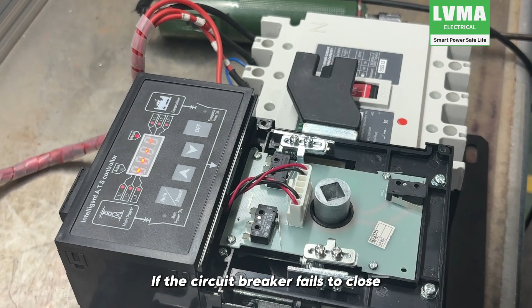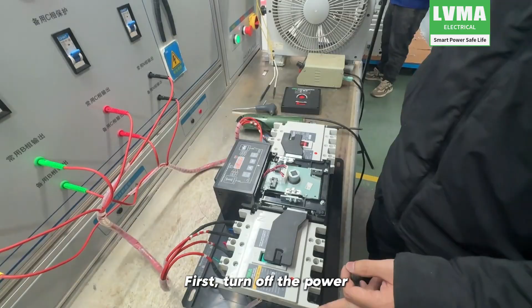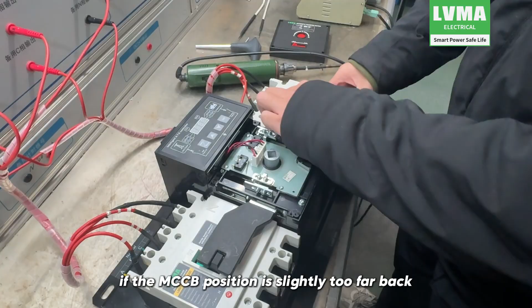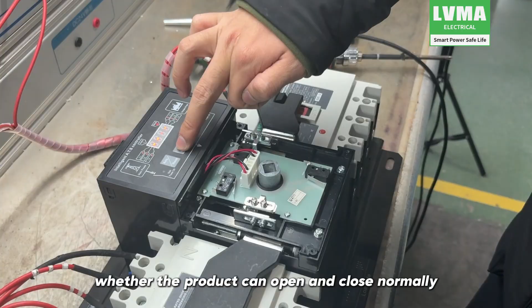Start testing. If the circuit breaker fails to close, adjust the forward and backward stroke of the product. First, turn off the power, then slightly loosen all tightened screws. In this case, if the MCCB position is slightly too far back, adjust it forward slightly. Then, retighten the screws. Power on again and verify whether the product can open and close normally.